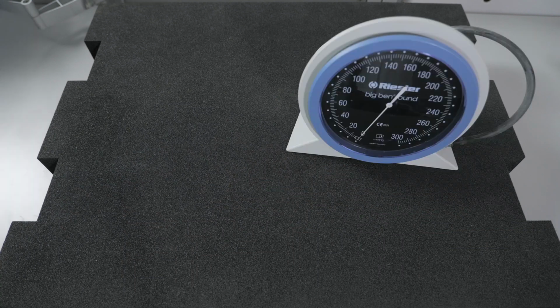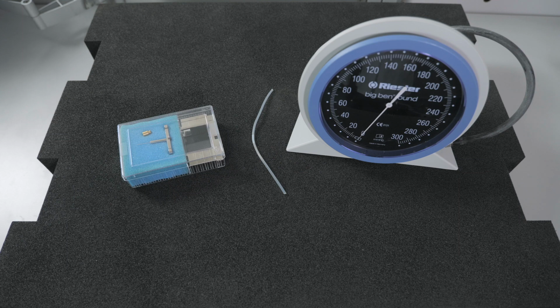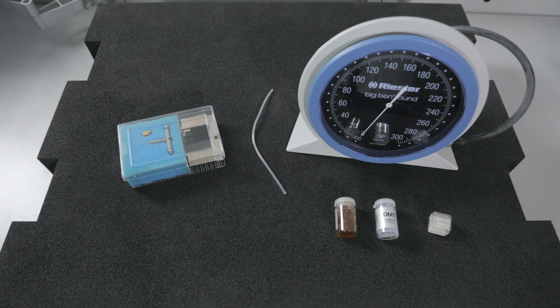For maintaining your system, you will be given a Big Ben round manometer, a calibration shunt, a force calibration kit, a pack of replacement cover glass, clear grease for maintaining the security around the force transducer, brown grease for maintaining the micro positioners, extra screws, and an Allen key for making adjustments.